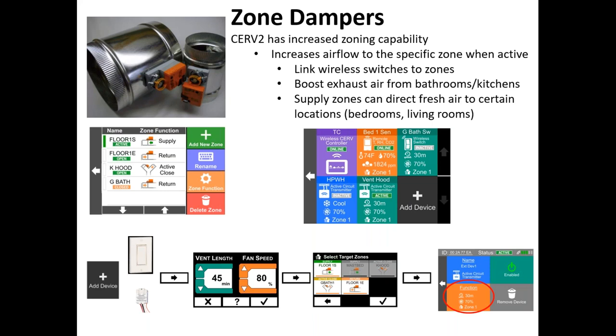That would let you target the airflow more specifically to the zone that is actively calling for ventilation. You can also do this on the supply side. Say anytime the master bathroom switch is pressed, if you had supply zone dampers, you could target the supply fresh air to go more specifically towards the master bedroom area. So you have flexibility this way as well for that targeted zone damper.